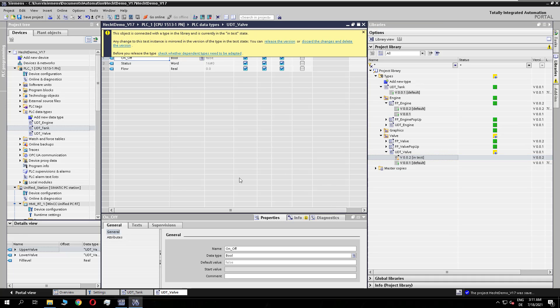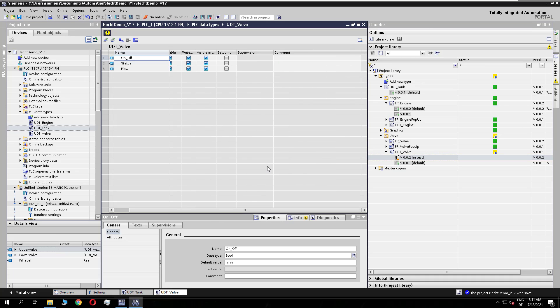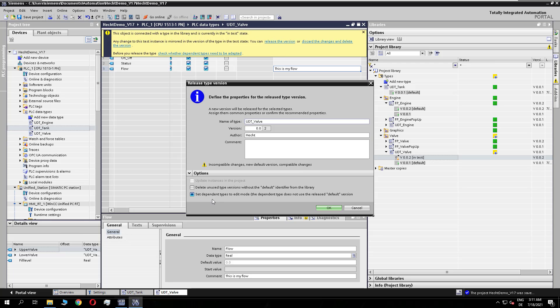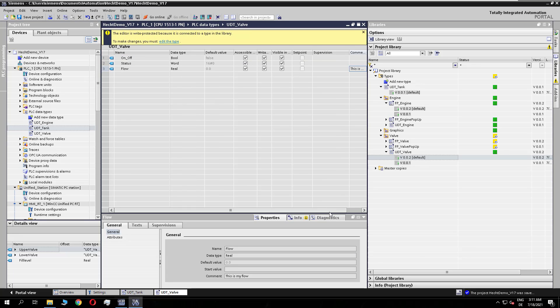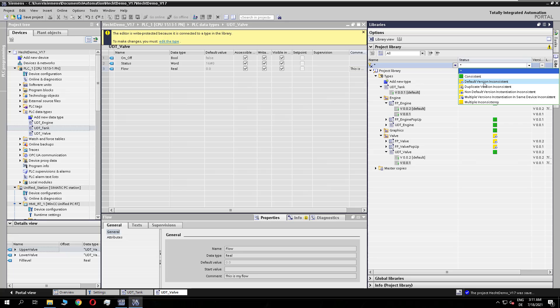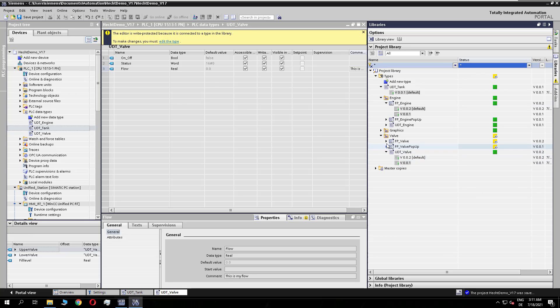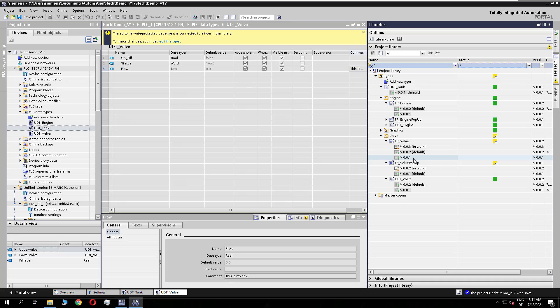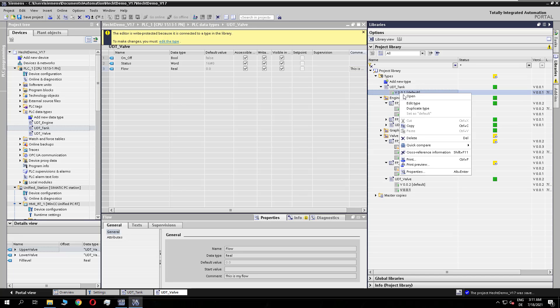Now I modify the UDT valve — we know it appears twice inside UDT tank. The first thing I do is add a comment. I want to show that this comment does not affect the dependency type of the tank. We see the face plates go yellow because we changed the UDT interface, and the default version is inconsistent, but the UDT tank which includes the valve has not changed version.